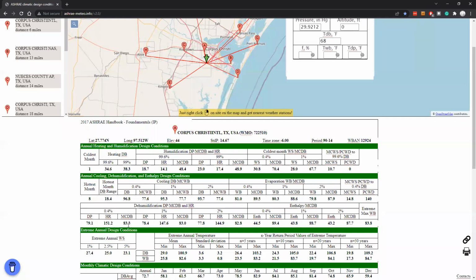And so they do the mean coincidental dry bulb on this side, and it's 83.3 degrees out on the most humid day, with a dew point of 79 degrees. If you want to turn that into a dry bulb, wet bulb, just use a psychrometric calculator—there's a bunch of free ones online. Just Google free psychrometric calculator and off you go.